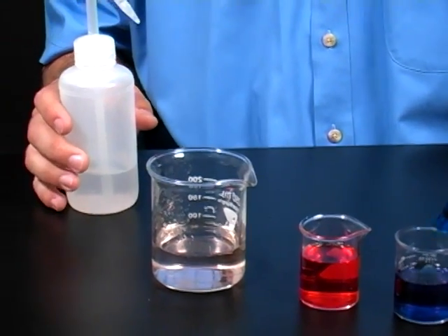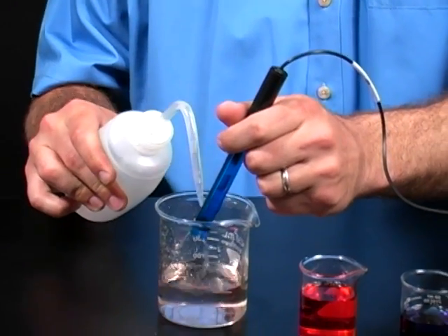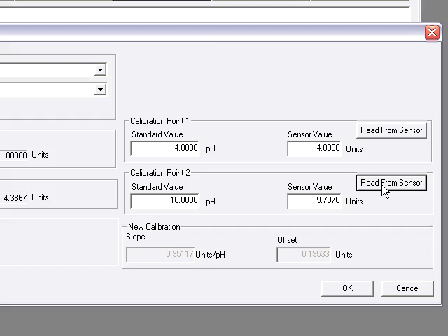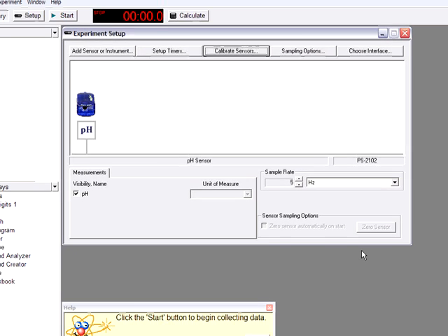We'll then remove the probe from that solution, rinse, and place it in our second pH buffer solution. In the calibrate sensors window, click the Read from Sensor button in the box corresponding to that pH value. Again, you'll notice that the sensor value has changed.